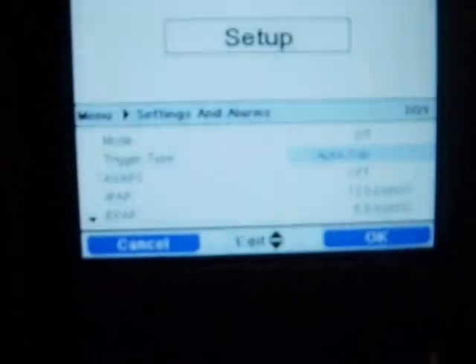When you are at home, normally we will help you set auto track, because the doctor and even us are not with you every day, every night when you use a ventilator. So we let the machine use this algorithm called auto track to help detect when you are going to inhale and exhale, and when a leak occurs, the machine will know how to compensate for the leak in the tubing system. So normally for adults we select auto track. For pediatrics we use auto track sensitive, or for those adults who have very low inspiratory effort, we use auto track sensitive. Okay, so we test this with you at home before we decide which one to use, and how you perform decides our final settings.